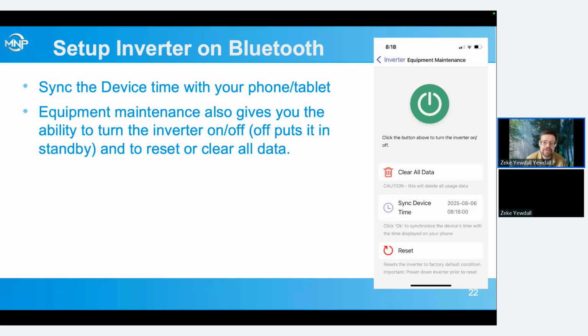First thing we want to do when setting up the inverter is go to the equipment maintenance screen, and we want to sync our device time with our phone or tablet. Also in this section, we have reset, clear all data, and turning the inverter on and off. Usually it's fine to just start and program our inverter, but there's times when we want to clear all the data, especially if we've got a lot of stuff set up incorrectly to begin with. We can get some weird data points that throw off all the graphs. One thing it does sometimes is say it's got like gigawatt hours of production, which doesn't make any sense for this size of inverter.